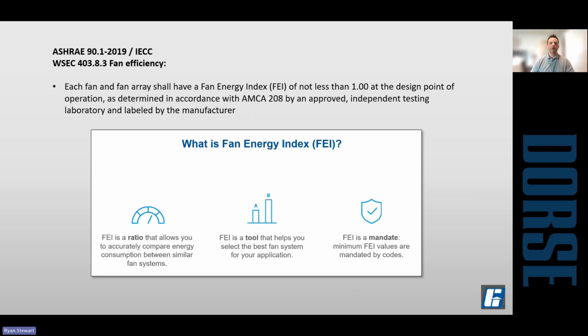So the Washington State Energy Code has a requirement for a fan energy index of not less than 1.0 at the specific design point of operation. This is going to apply for any fans that are over 1 horsepower. It's a ratio that allows you to compare the energy consumption between similar fan systems, various models and manufacturers of fans. It's there to help you select the best fan for the system and application. And it is a mandate in any of those 14 states that are on ASHRAE 90.1. So you're going to start to get requests from jurisdictions to have FEI as a part of your fan schedule.